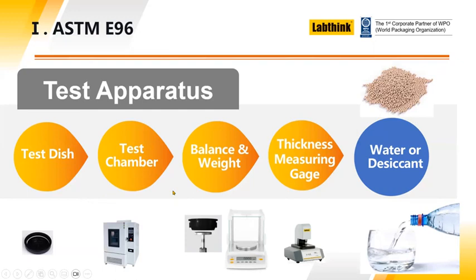So the components of a system or apparatus for performing these tests consist of some kind of test dish, you could call it a dish or a cup, a chamber in which to place the dishes with the specimens mounted, and inside the chamber is a temperature and humidity controlled environment. And then we need some way of weighing accurately the small changes in weight that are experienced as the water evaporates or the desiccant increases in weight. And then finally, we need a thickness measurement gauge to measure the thickness of the material accurately, and some distilled water or some desiccant. So these are the fundamental components of an ASTM E96 test system.